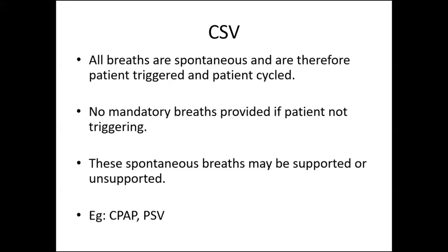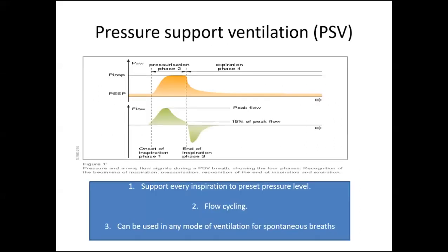In spontaneous ventilation, it is the patient who is controlling the cycle variable, and the ventilator can detect it only by flow, not by time, because the patient can vary the time. Each time the ventilator cannot detect the patient's time. So that's why you tell the ventilator to use the flow. You always need to set the flow, either 15%, 20%, 25%, 30% of the peak flow. If you set that and the flow from the peak flow reaches 20-30%, it will switch over to expiration.